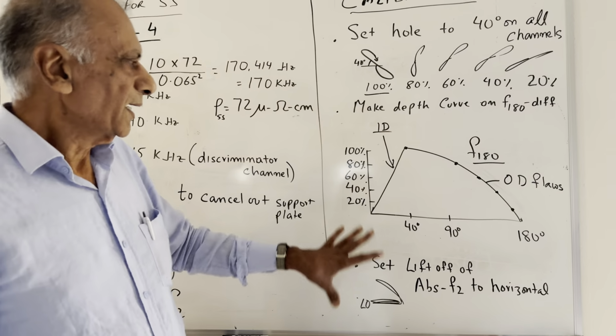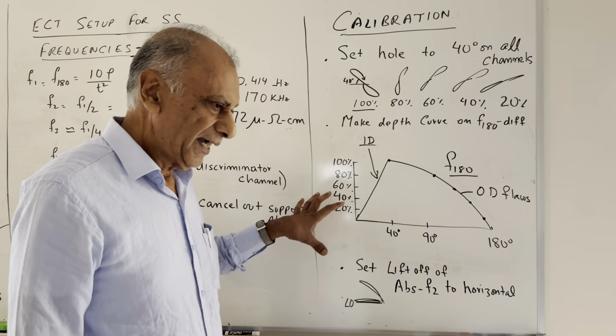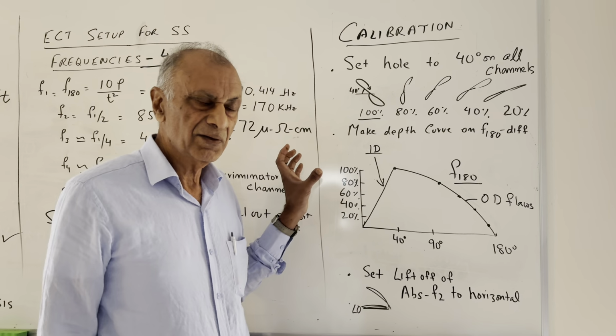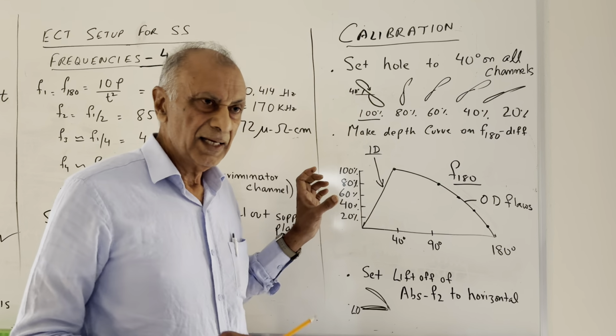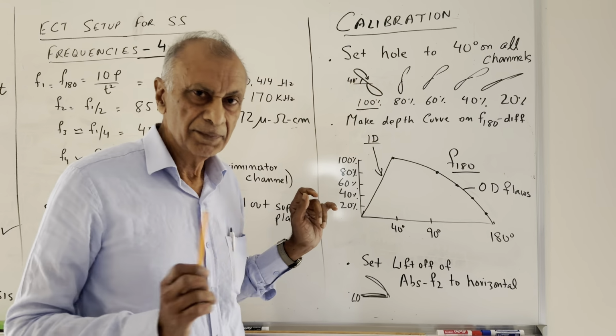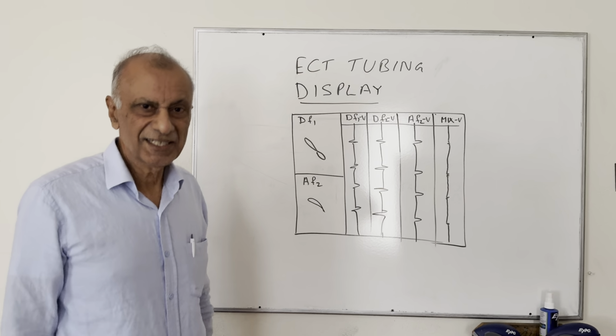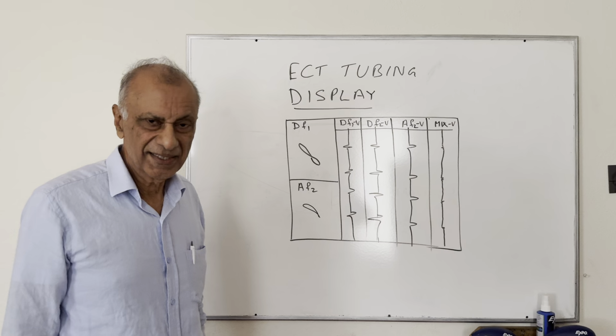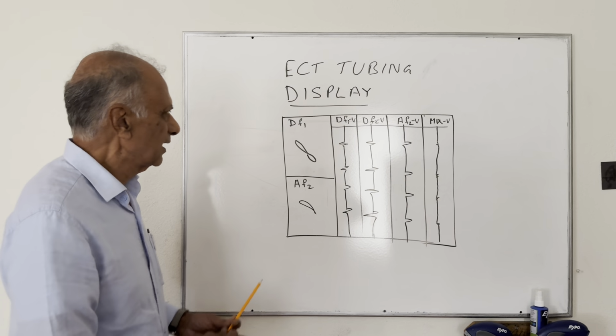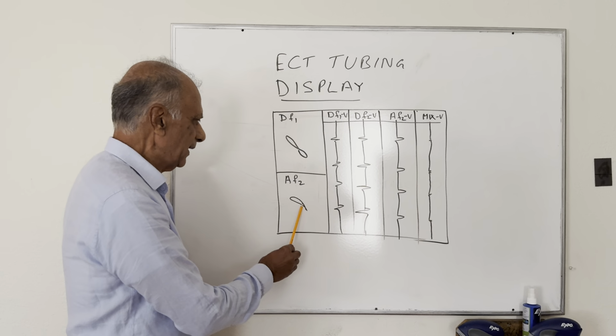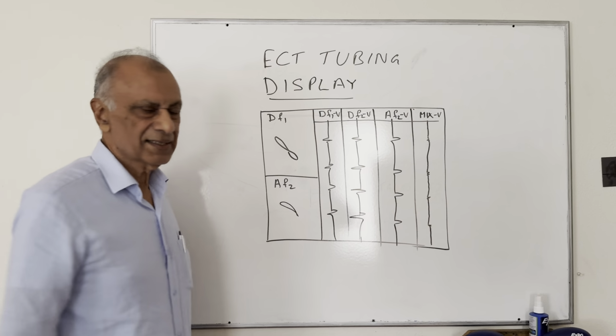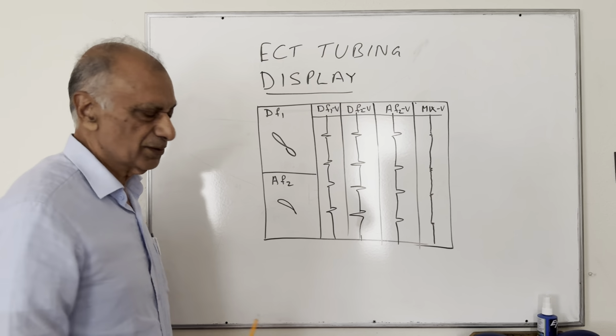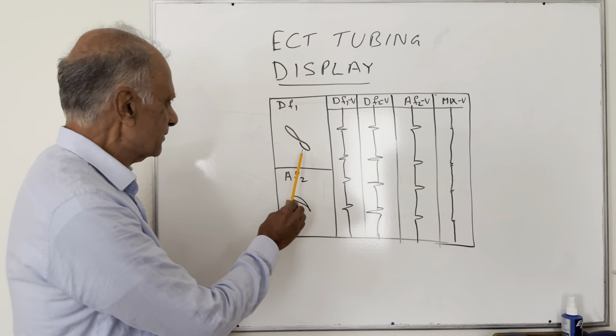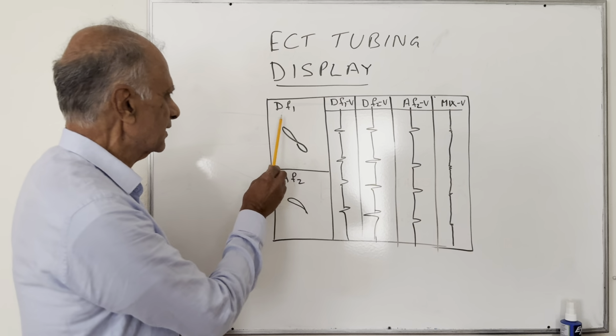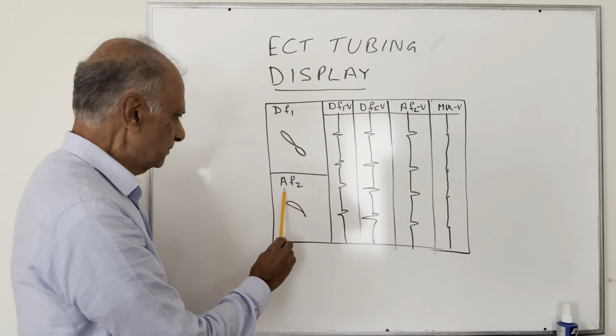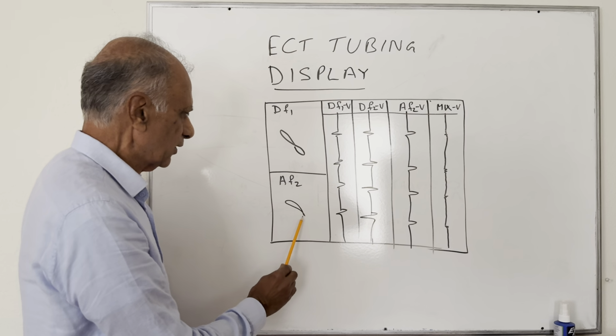So this is how you actually do the calibration, and then the final display will be on the ECT machine, and let me show you that on a different board. So the final ECT display on your multi-frequency eddy current machine should look like this. You will have 2 impedance planes and 4 strip charts. That's the option you should select because there are many options on those machines.